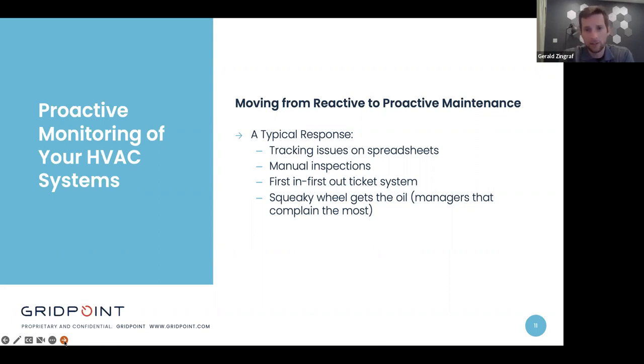The last option here is, I think, probably something more familiar to a lot of folks, which is we get more tickets than we'd like. We get more tickets than we have the capacity to address. So the squeaky wheel gets the oil. The sites that are complaining the most, four, five, six calls that week, that becomes priority. The loudest sites tend to be what we would consider most severe. That doesn't always line up with reality. Again, this is an issue of perception versus reality. And that's where having data to move to a more proactive maintenance strategy could be very helpful.